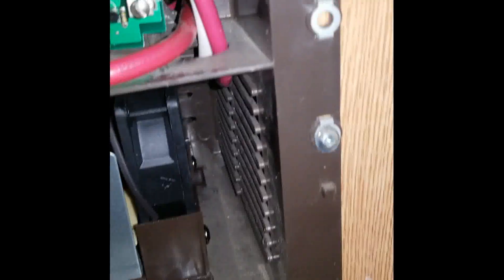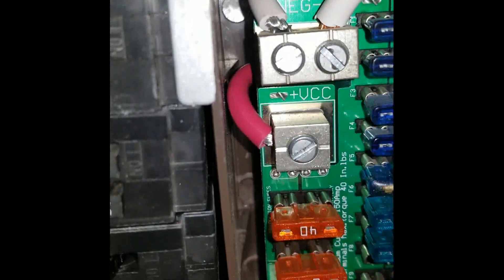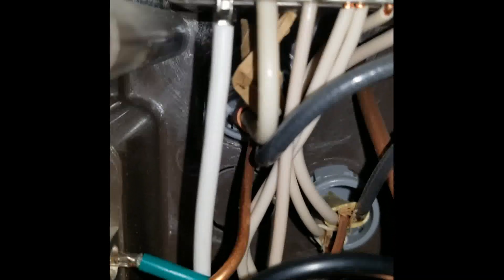Old unit out, and running the new one in underneath. Just make sure you route all the wires back — the two went behind the board and then came out over here. The 120-volt wires go back there — common, neutral, ground through the middle plate. The black went to the circuit board and had the jumper pigtail wire nut, and then you've got your common, or your neutral, there on top — common up there on the common board.